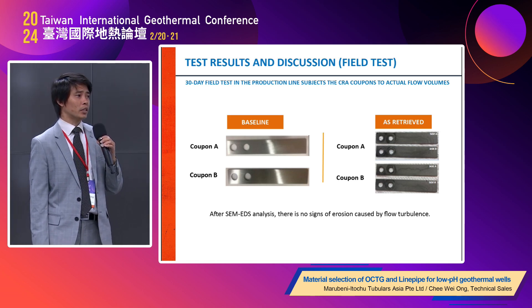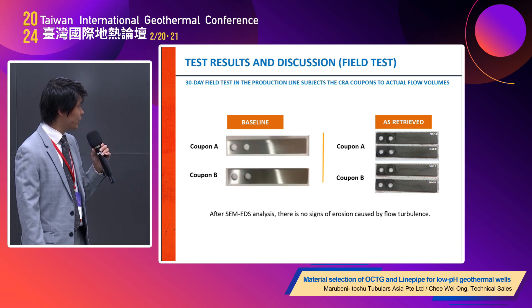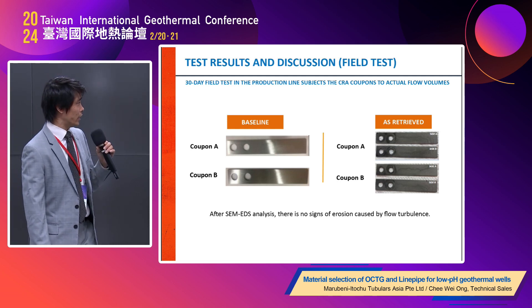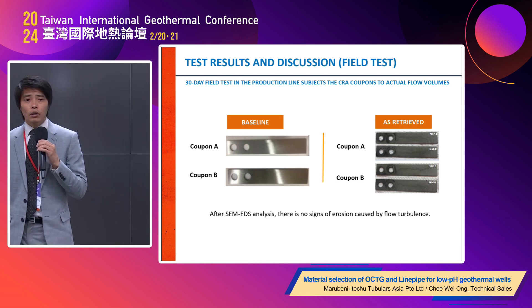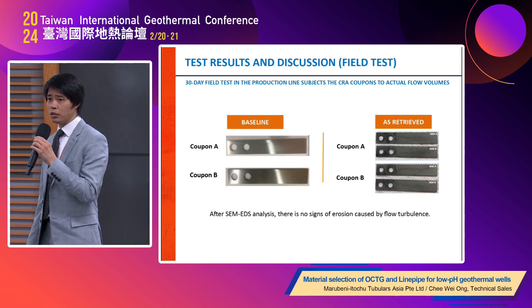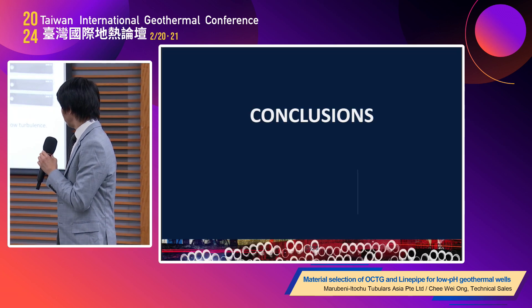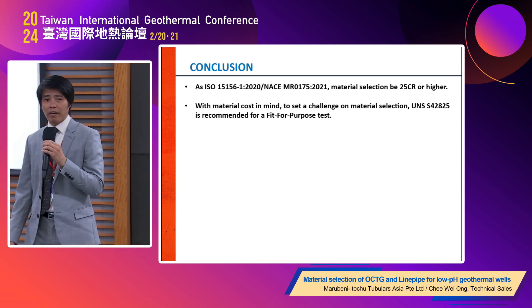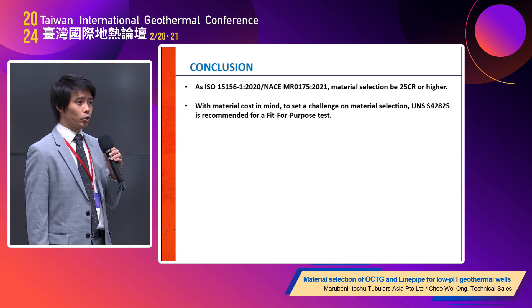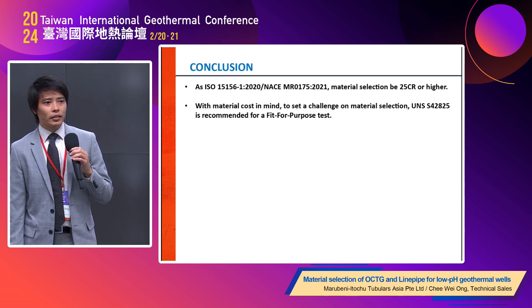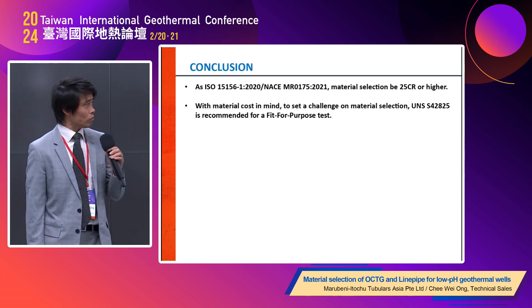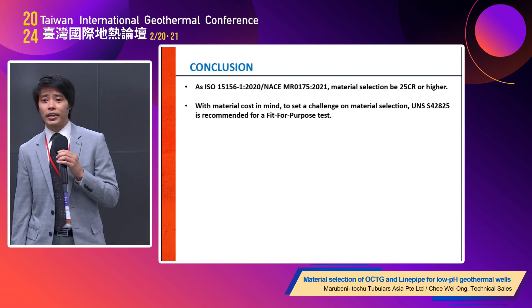In the field test, supporting the lab results, coupons were immersed for 30 days. The baseline shows material not yet placed in the production line, while the retrieved coupons showed no erosion due to flow turbulence. Conclusions: per ISO 15156, material selection points to 25-chrome. With material cost optimization in mind, UNS S42825 is also considered, and a fit-for-purpose test is needed to justify this recommendation.